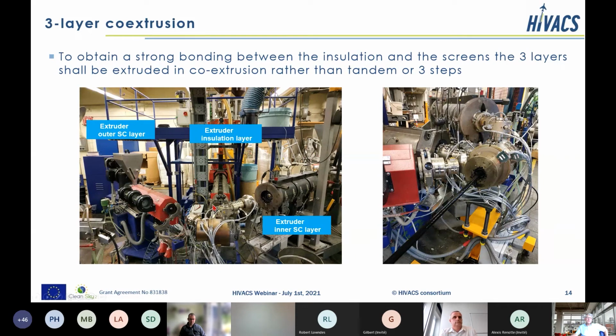So here we see the extrusion line with the main extruder in the middle for the insulation, and on the left and on the right, the extruders for the insulation screen and the conductor screen. Those 3 extruders are connected to the extrusion crosshead. Here from the right hand we have the conductor, which goes inside the extruder, and on the left hand, that's the exit of the crosshead. We have the insulated wire with the 3 layers: conductor screen, insulation, and insulation screen.